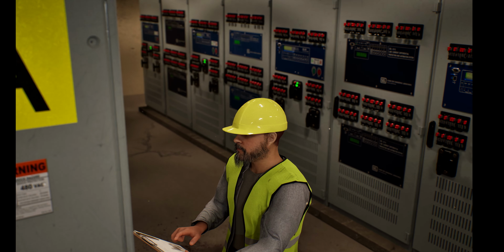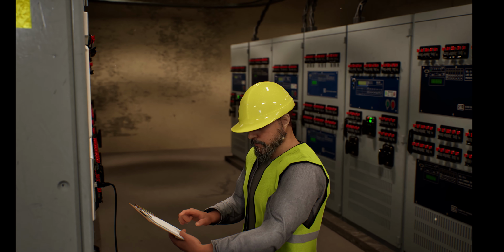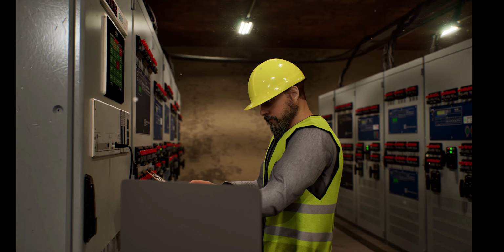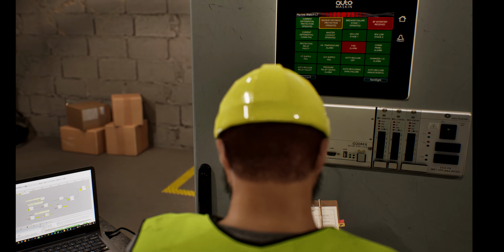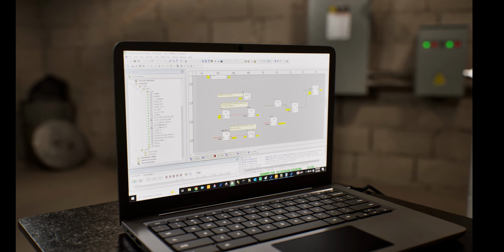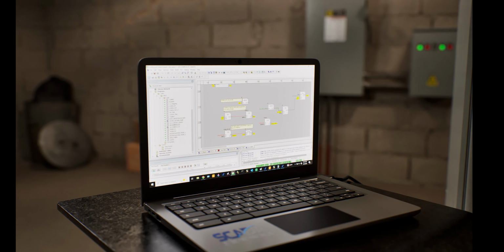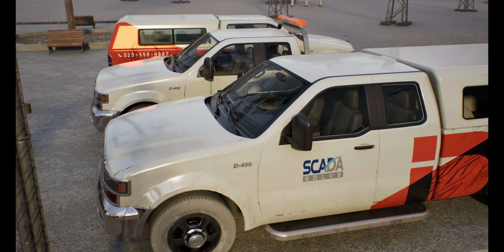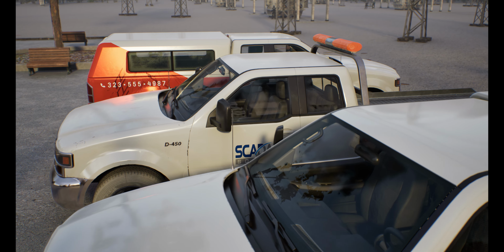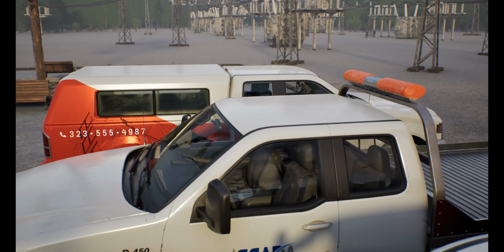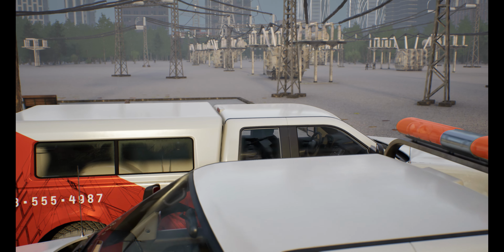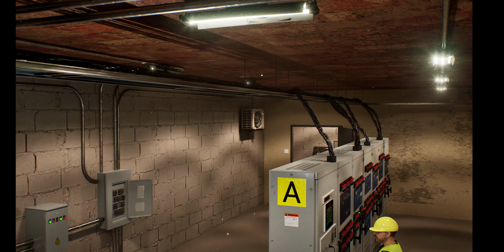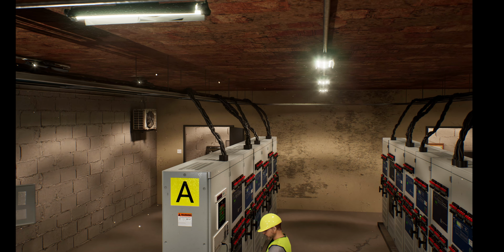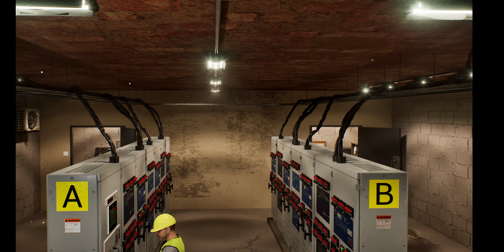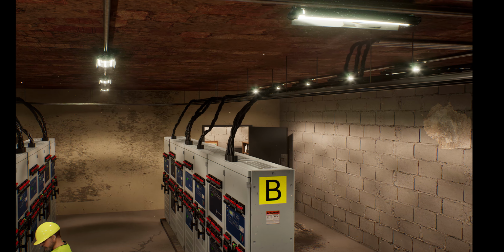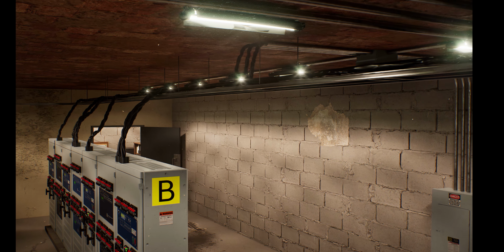Personal protective equipment, or PPE, is a critical layer of defense. NFPA 70E requires PPE to be selected based on the task, the equipment condition, and the level of electrical hazard present, including arc flash and shock risk. Required PPE may include flame-resistant clothing, hard hats with appropriate electrical ratings, eye and face protection, voltage-rated gloves with leather protectors, and electrical hazard-rated footwear. PPE must be inspected before use. Damaged or compromised equipment must never be worn.